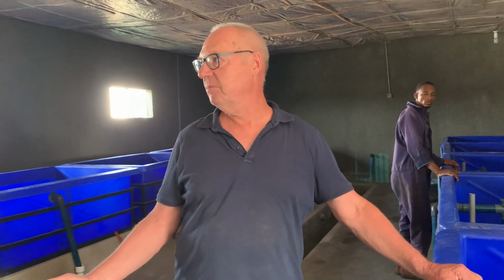And here the borehole is quite good, no iron, and there's not much contamination in this area because we are in the middle of nowhere. So I don't suspect any bacterial contamination. I expect good water here. Hence, you don't need a UV, right? No, because the water is clean. The calcium content is also not very high. I tested the calcium content.